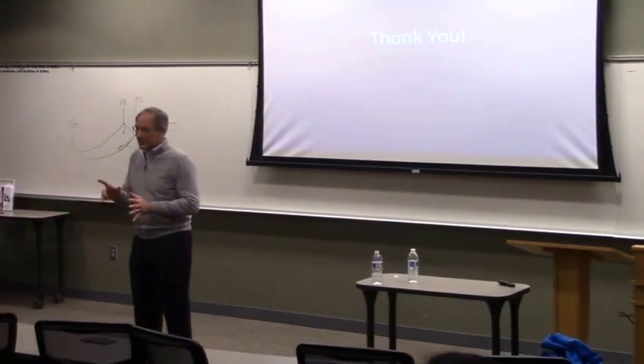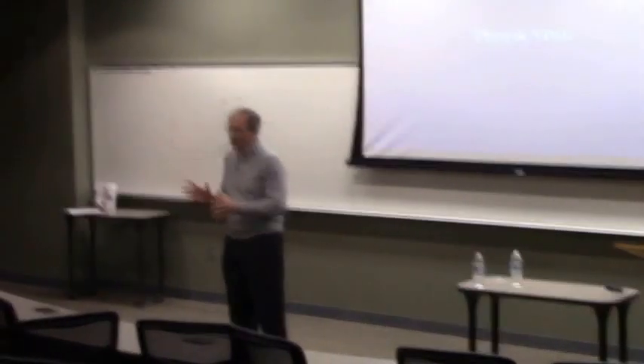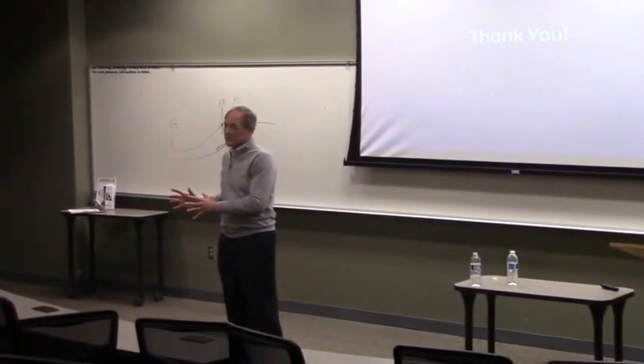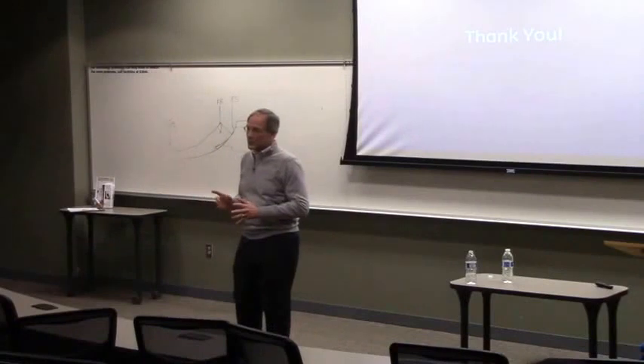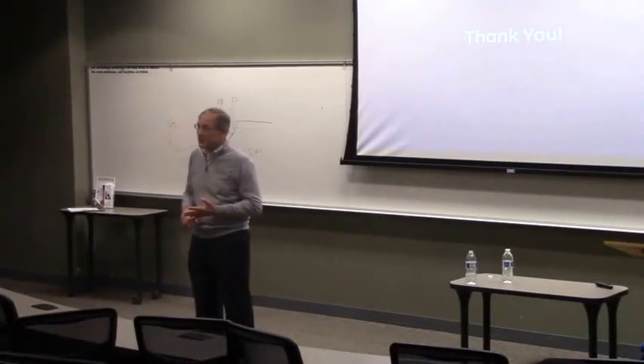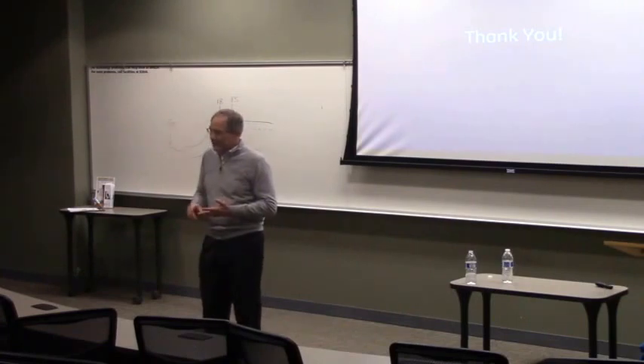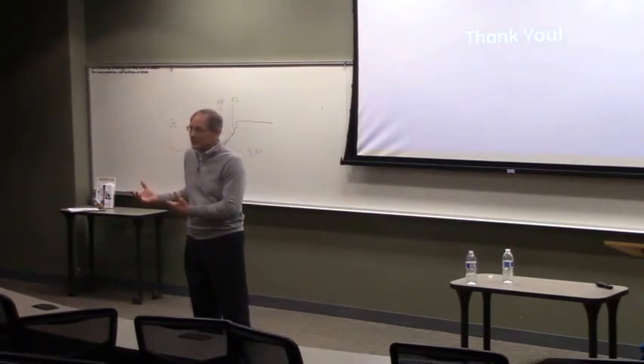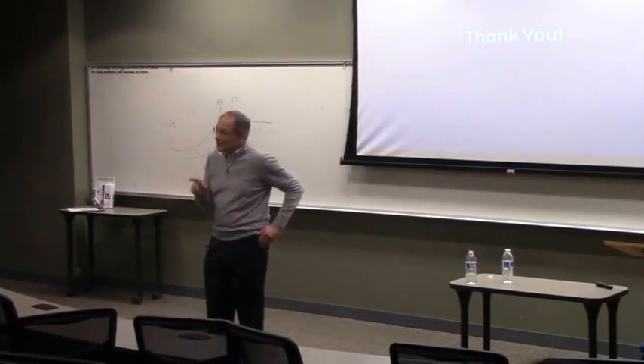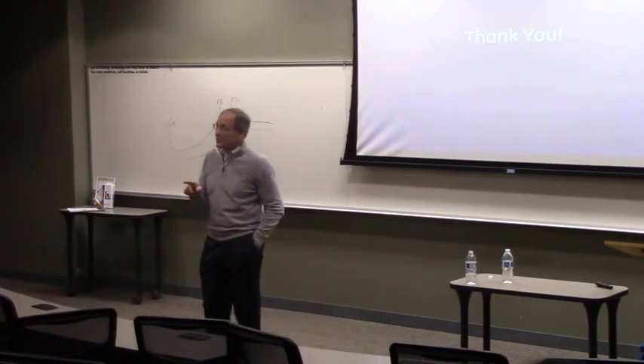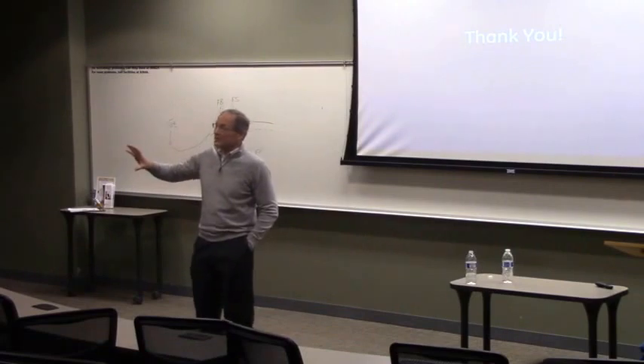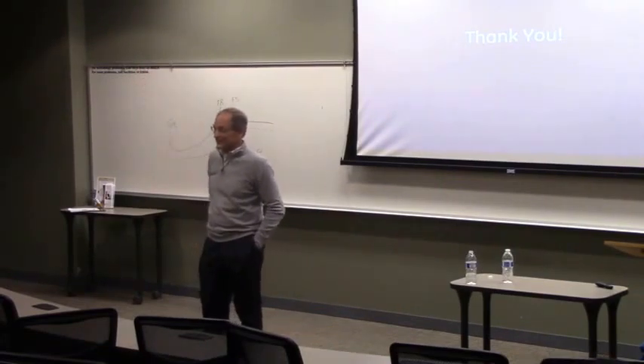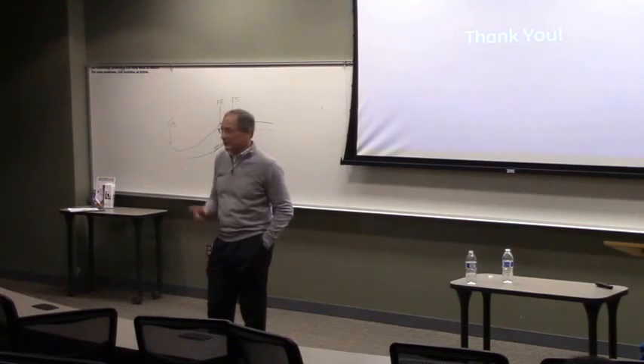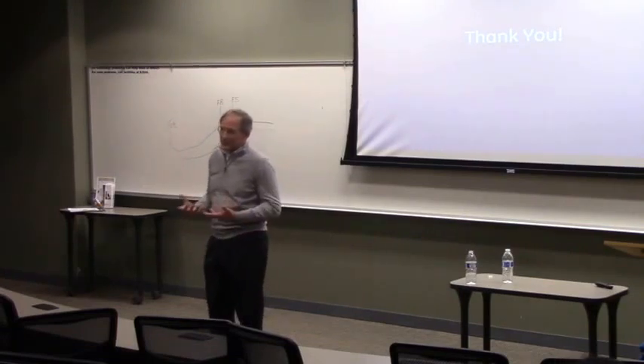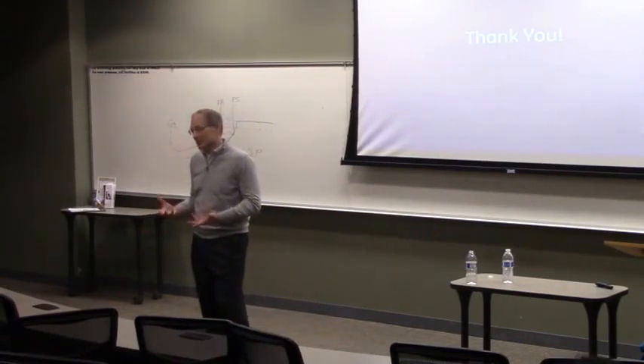Eventually, I see 61850 for certain substations replacing DNP. Those are the more critical substations where you need peer-to-peer communication and can afford Ethernet networks. For smaller substations, like distribution substations, 61850 would be overkill, so you stay with DNP. But as we get more experience with 61850, I see it being used as the protocol from the substation up to the control center.